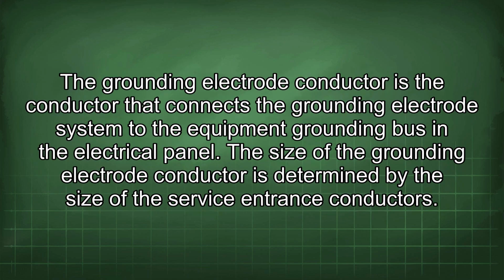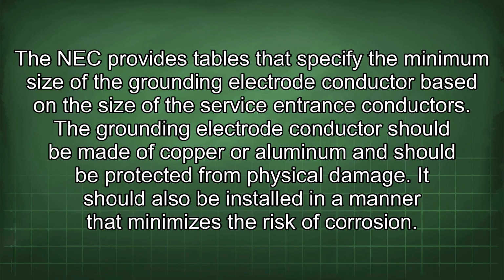The grounding electrode conductor is the conductor that connects the grounding electrode system to the equipment grounding bus in the electrical panel. The size of the grounding electrode conductor is determined by the size of the service entrance conductors. The NEC provides tables that specify the minimum size of the grounding electrode conductor based on the size of the service entrance conductors. The grounding electrode conductor should be made of copper or aluminum and should be protected from physical damage. It should also be installed in a manner that minimizes the risk of corrosion.